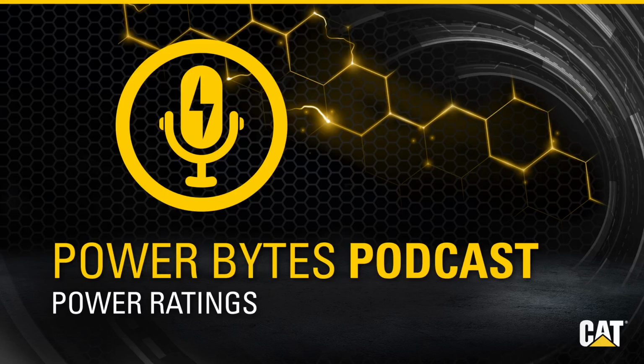Can you start us out with a brief definition for generator ratings and why we even have them? Certainly. Generator ratings are made up of two primary components. There's a numeric value, which describes the amount of power that we can get out of a specific product. And then there's the named rating category, which describes the operating conditions. These are things like the load factor or the hours of operation that we can get out of a product in a given year. Together they define the operation of the genset and how that impacts the overall life of the generator and even the maintenance intervals that we expect to see. So the ratings become an important part of how a user determines which one to buy.